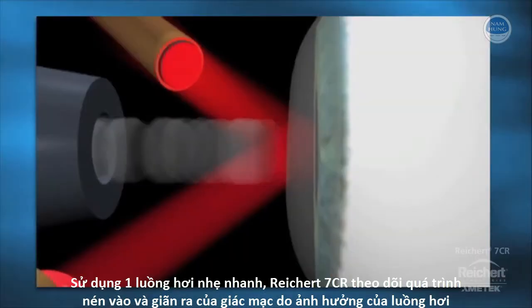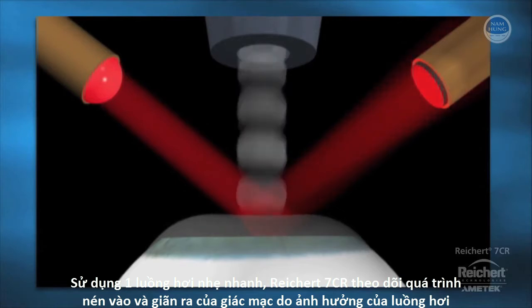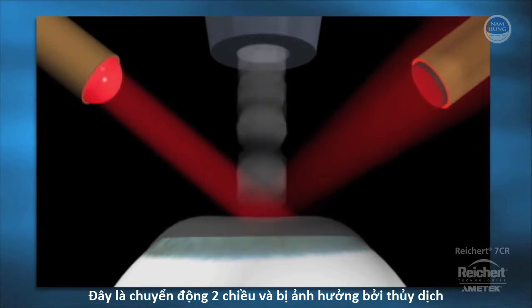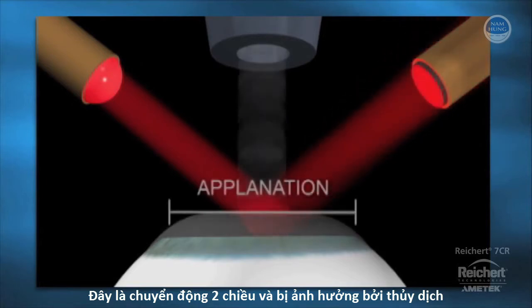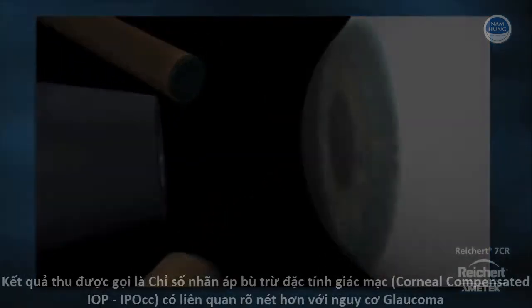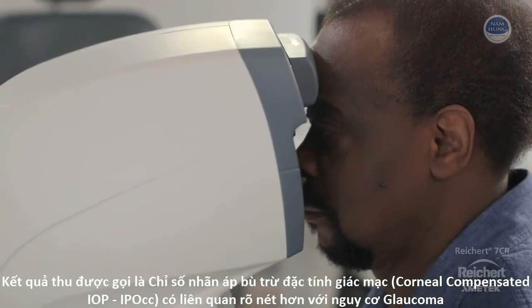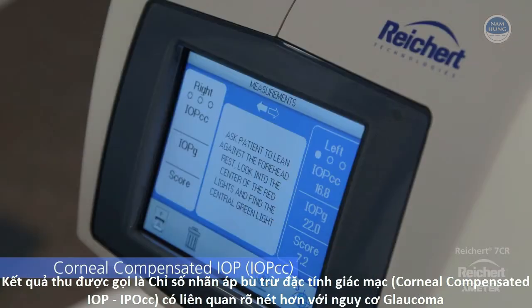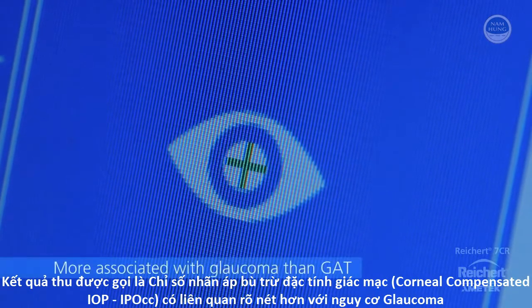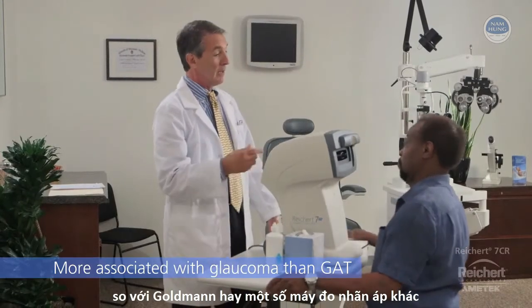Using a rapid air impulse, the Reichert 7CR monitors the inward and outward movement of the cornea. This dynamic bidirectional applanation process enables determination of corneal viscoelastic properties. The resulting measurement, called corneal compensated IOP, or IOPCC, has been shown to be more associated with glaucoma risk and progression than Goldmann or other tonometers.